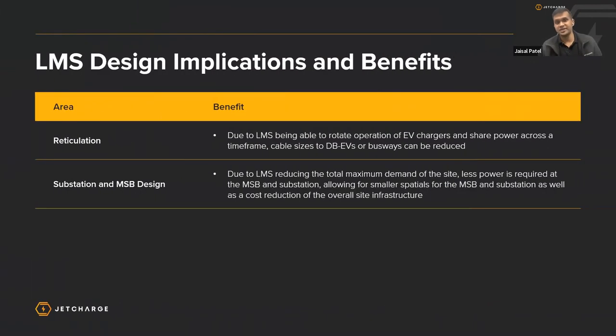So because we have put in a much lower maximum demand, it has a few implications. The load management is able to rotate operation of the EV chargers and share power across a time frame. Cable sizes to the distribution boards that are dedicated to EV chargers and the busways that we may potentially install in the future are reduced, which essentially brings down the cost of infrastructure for provisioning. The substation obviously would go down in size as well, because we do not require a larger substation to accommodate the power usage for the site. And we would require less space for the MSB room. So we do not require a larger distribution board that has to be custom built. We can just go with an off-the-shelf MCB chassis distribution board that is able to 100% provision for the whole car park. Next slide.